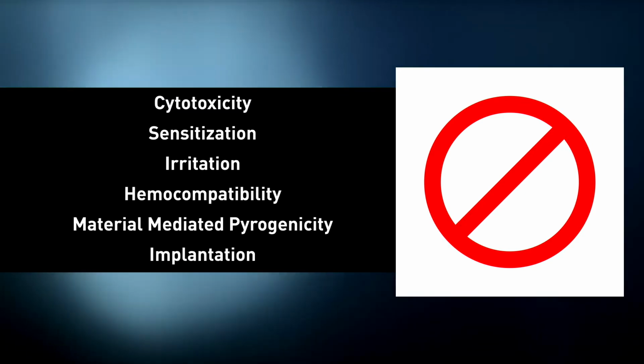Also, because the safety limits used within the tool have only been established for systemic biocompatibility endpoints, the tool cannot address local endpoints such as cytotoxicity, sensitization, irritation, hemocompatibility, material-mediated pyrogenicity, or implantation.